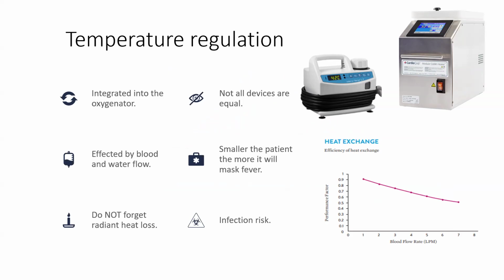It's affected by blood and the water flow. And a lot of people forget that even though you're heating and cooling a patient through the oxygenator, you still have radiant heat loss out through the patient themselves if you don't cover them up. Not all devices are equal. You have some, like the little white MicroTemp LT, that's not going to heat and cool your patient as effectively as the one on the right, which is the CardioQuip modular heater cooler. They each have their own power and gallons per minute that they're able to push through the system.